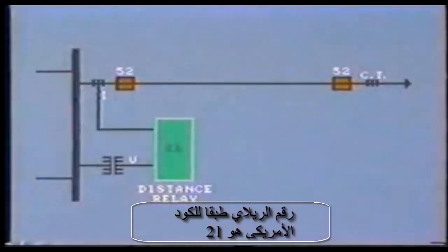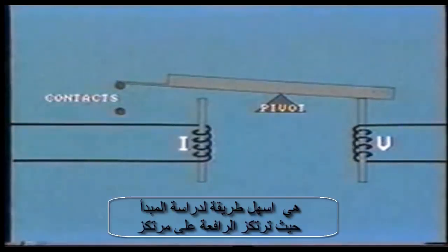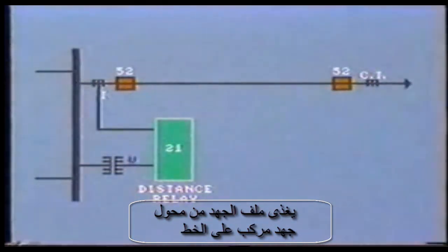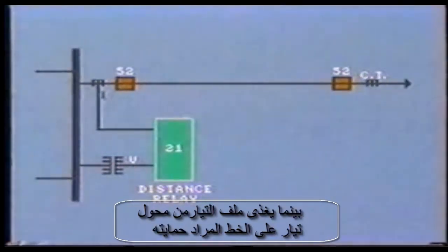The device number for the distance relay is number 21. The earlier types of distance relays worked on the balanced beam principle, and this is the easiest way to study the concept. The beam is pivoted like a seesaw with voltage and current coils at opposing ends. The voltage coil is fed from the voltage transformer on the line, or more usually on the bus feeding the line, while the current coil is fed from the current transformer on the protected line.